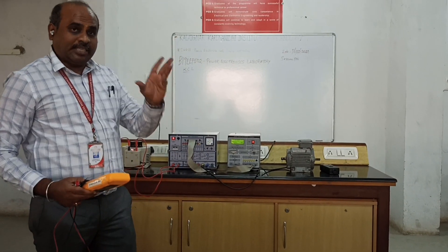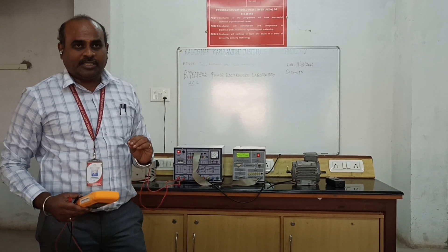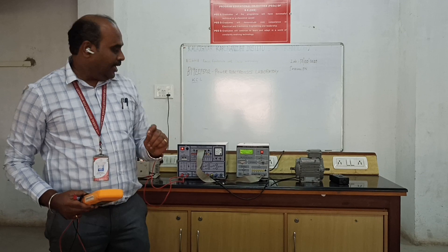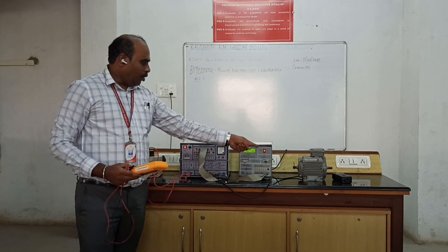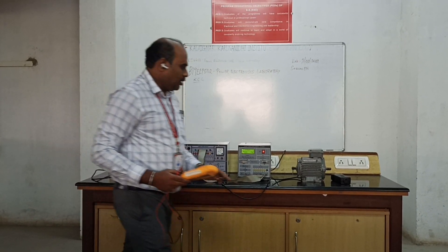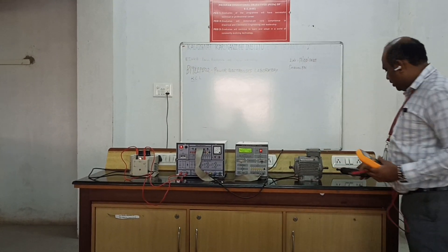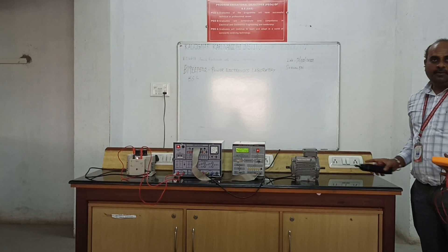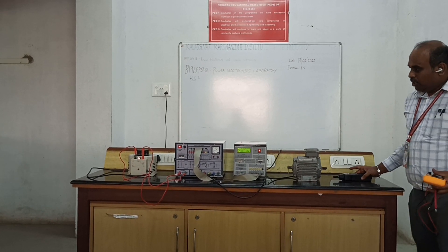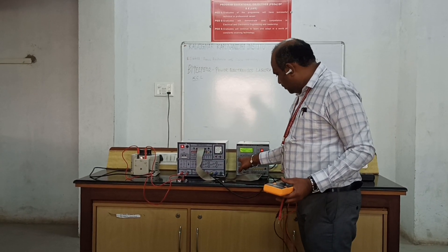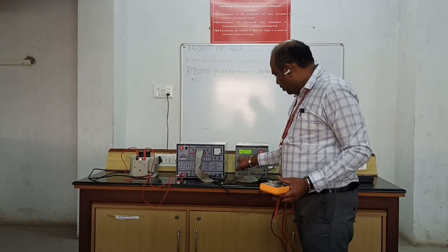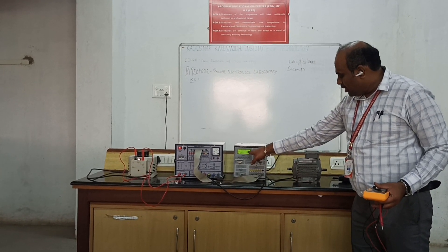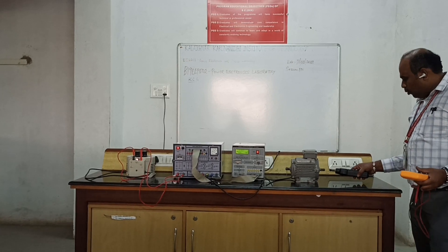The duty cycle is also important — it is defined as the ratio of on-time to total time. The motor is running; pulses are being given to the induction motor. At 20 Hz frequency, the modulation index is 0.38, giving a very slow speed of about 250 RPM. We now use the increment key to increase the frequency.